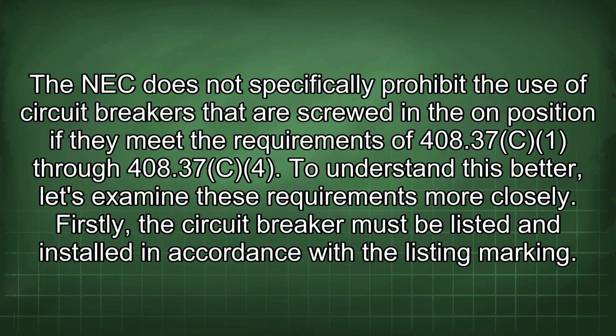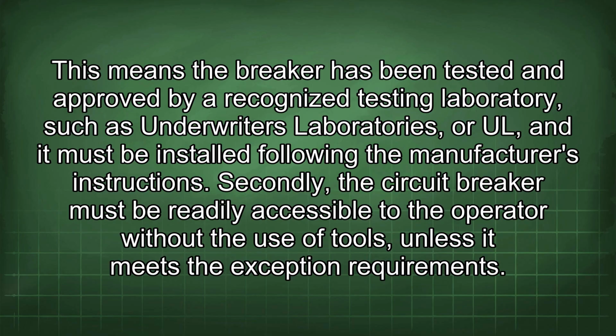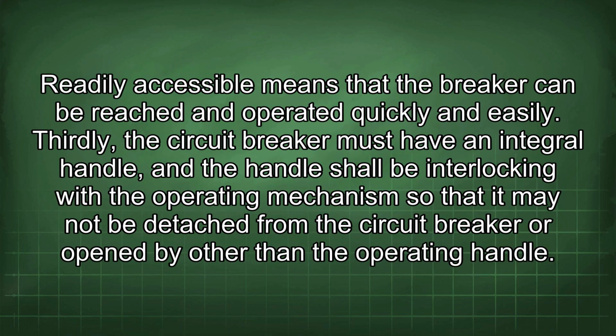Firstly, the circuit breaker must be listed and installed in accordance with the listing marking. This means the breaker has been tested and approved by a recognized testing laboratory such as Underwriters Laboratories, or UL, and it must be installed following the manufacturer's instructions. Secondly, the circuit breaker must be readily accessible to the operator without the use of tools, unless it meets the exception requirements. Readily accessible means that the breaker can be reached and operated quickly and easily.